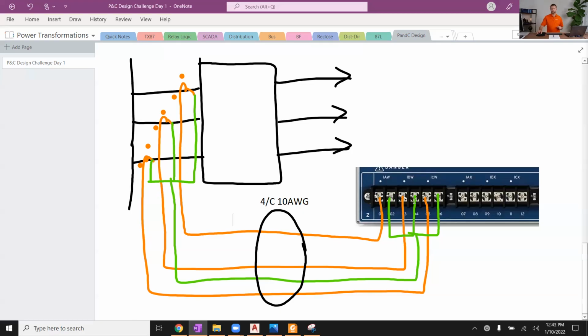Now, in reality, we're going to add more to this equation shortly. We're going to start talking about test switches and terminal blocks. In reality, we don't wire the back of the terminals of the CT directly to the terminals of the relay. There's more in the middle. Somebody's pointing out a good point. Where do we ground the CTs? You're absolutely right. I was going to cover that later, but since you asked, I will throw that in here now.